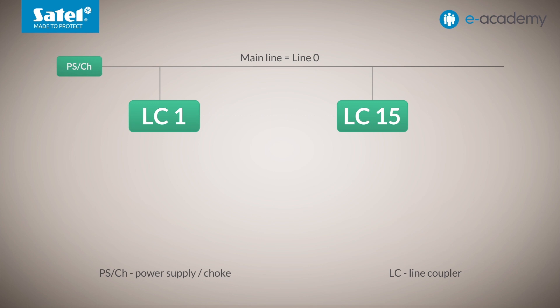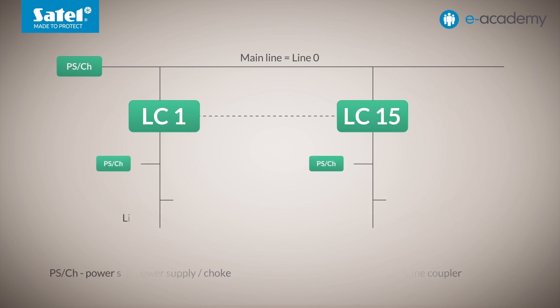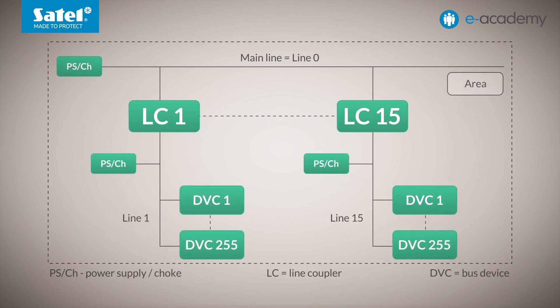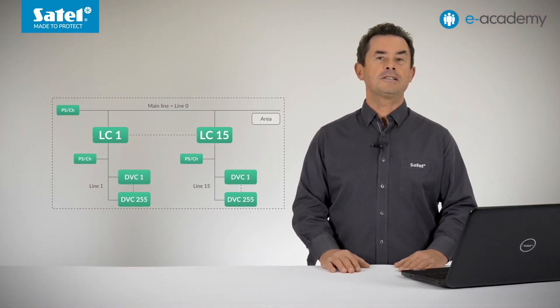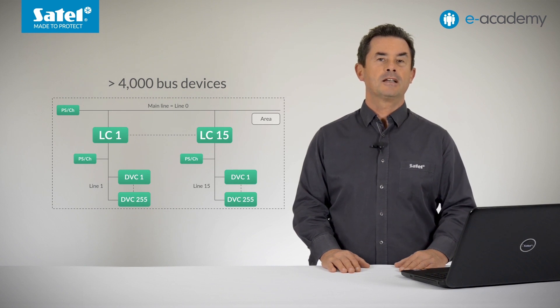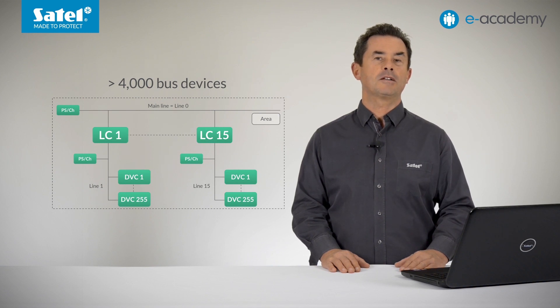The structure created in this way — containing the main line and no more than 15 secondary lines coupled to it — is called an area. A maximum of 255 devices can be installed in each of the secondary lines. The primary line, on the other hand, can have one more device, for a total of 256. However, the number of all line couplers operating in an area must be deducted; the maximum number of these is 15. To sum up, a total of up to more than 4,000 bus devices can be installed in a single area. In addition, separate power supplies are provided for each line, both main and secondary.